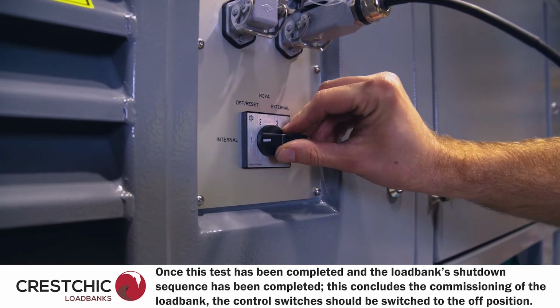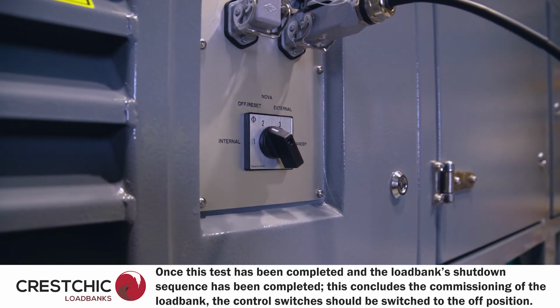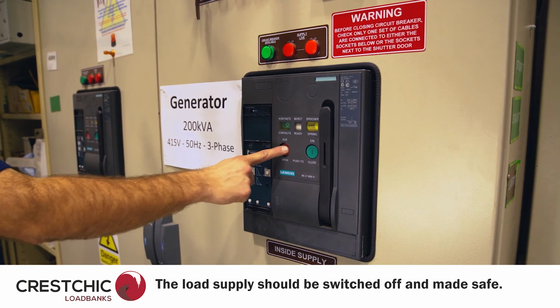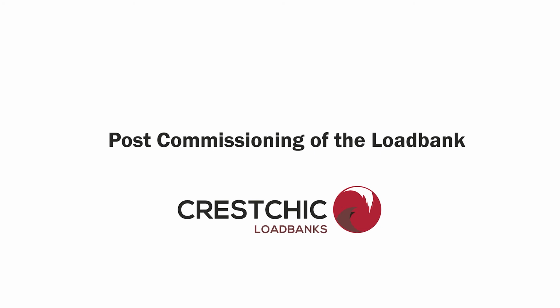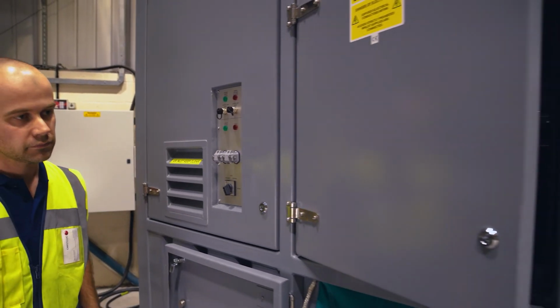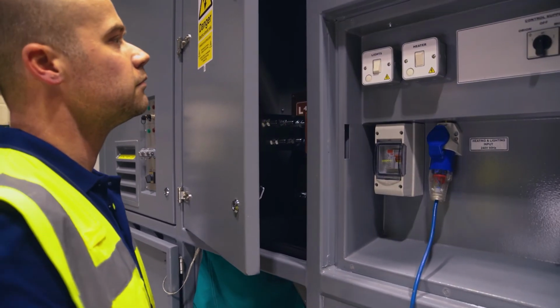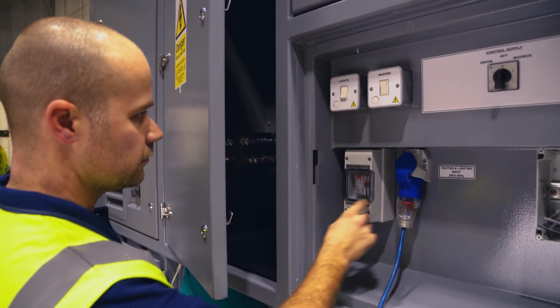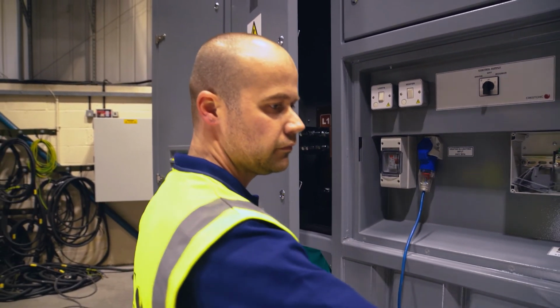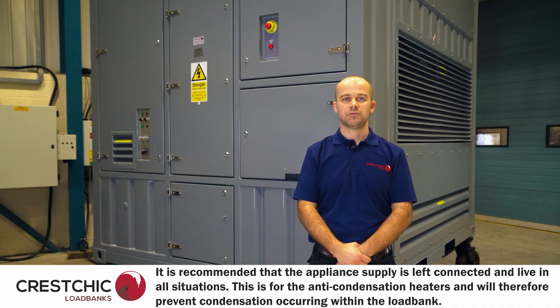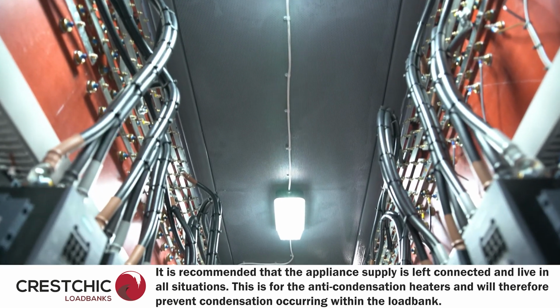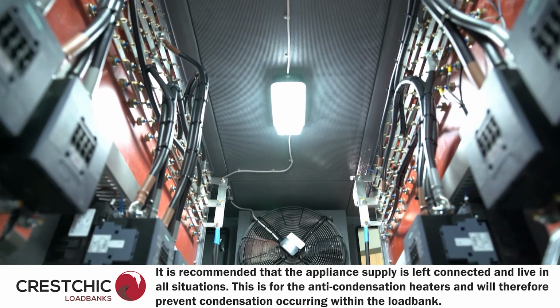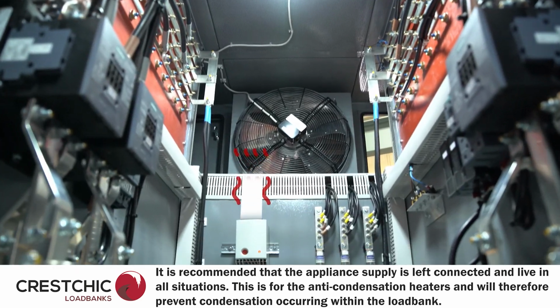The control switches should be switched to the off position. The load supply should be switched off and made safe. Depending if the load bank is permanently installed or is temporarily installed, the auxiliary supply and appliance supply can be left connected and live. It is recommended that the appliance supply is left connected and live in all situations. This is for the anti-condensation heaters and will therefore prevent condensation occurring within the load bank.